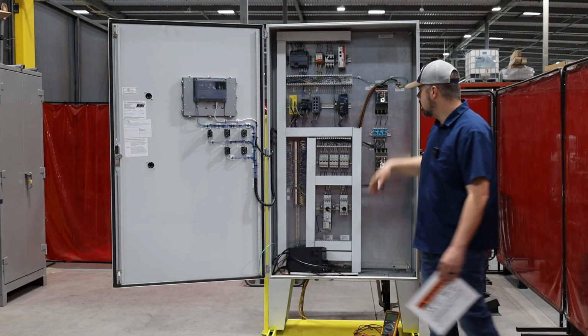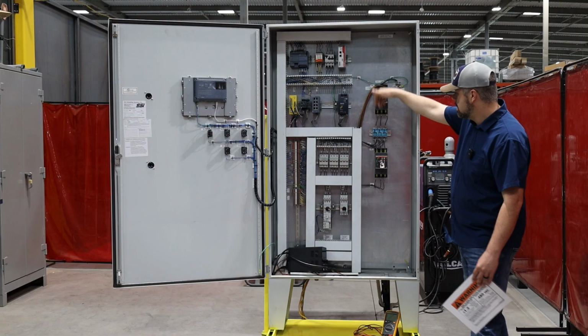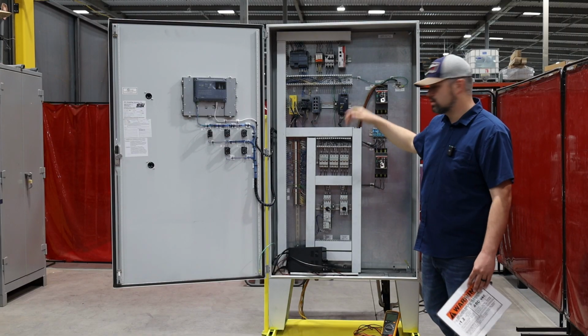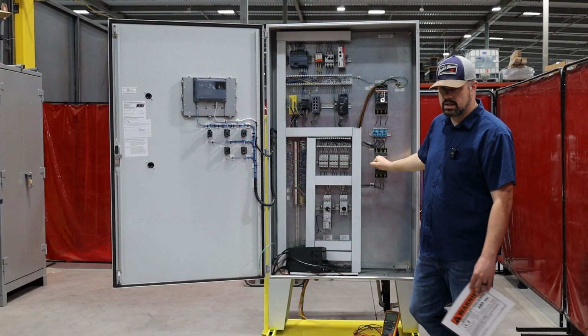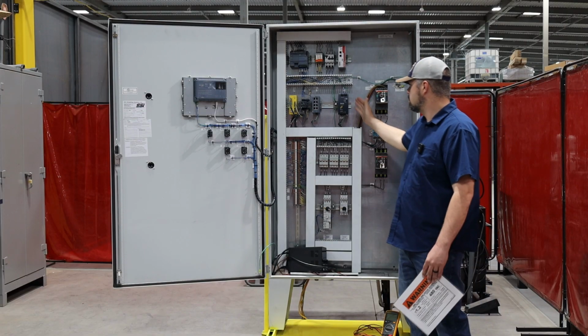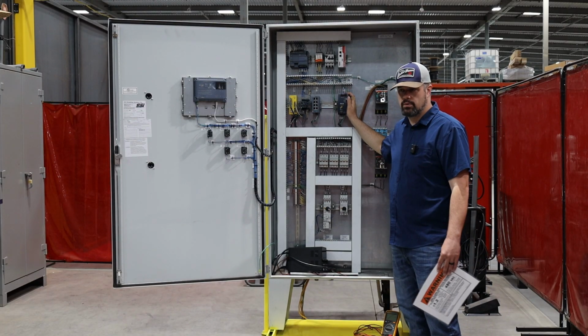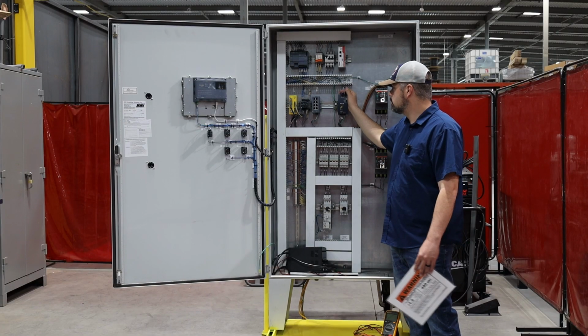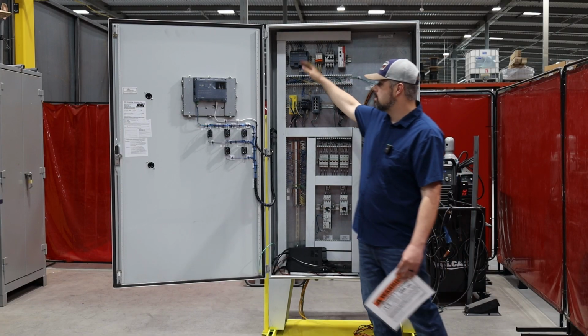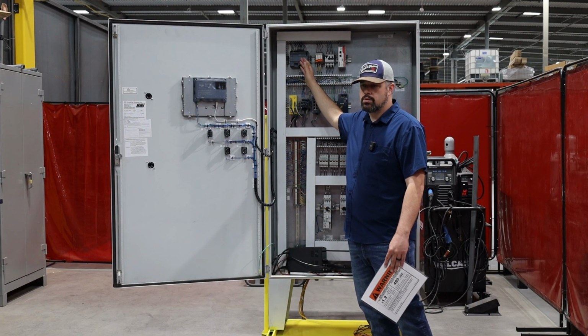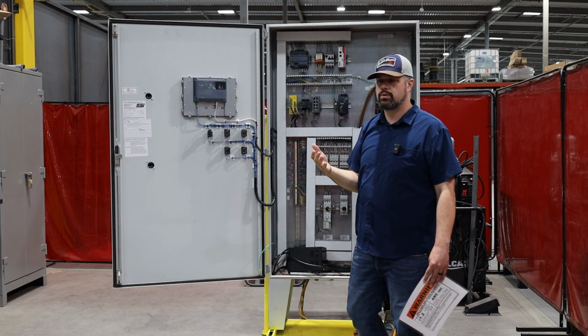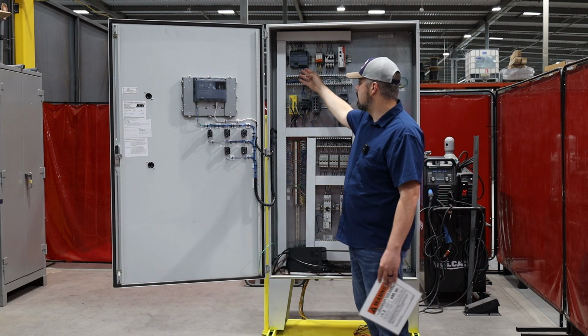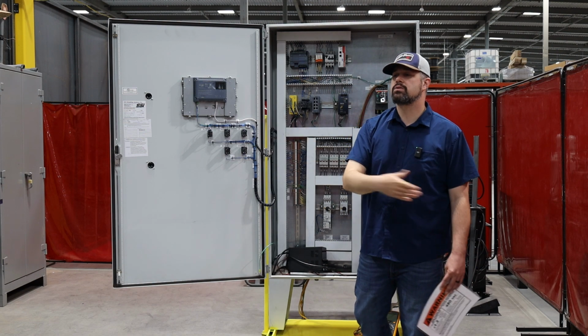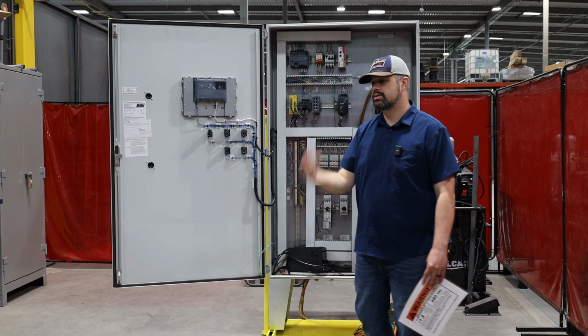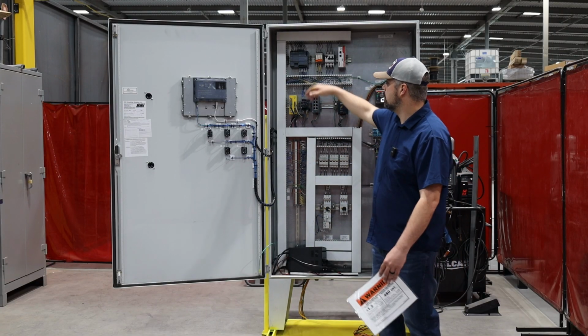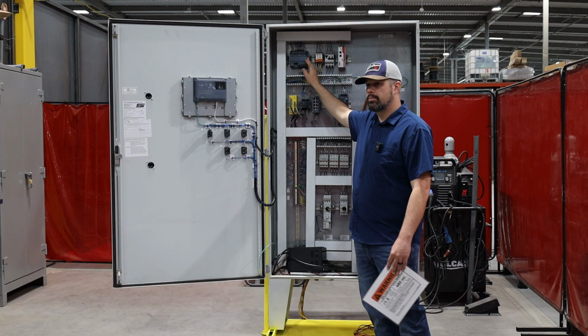You'll understand, 480 comes in right on the top of this disconnect. It comes out, it distributes off to many different circuits, whether it be down here to another disconnect for an individual pump. It goes off to this power supply, which takes 480 volts AC and drops it down to 24 volts DC, which will come over here to the PLC, right, programmable logic controller, and give that PLC the 24 volt DC power that it needs. And this goes off with all its different sensors in the field, all those field devices, level sensors, flow sensors, coming back, bringing that information back to the input of the PLC, right?